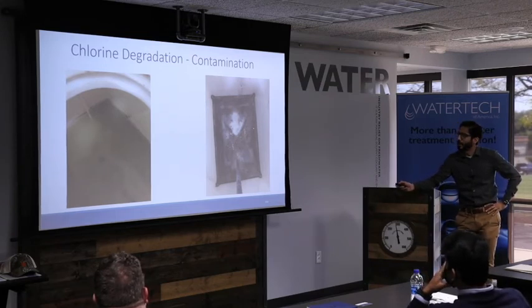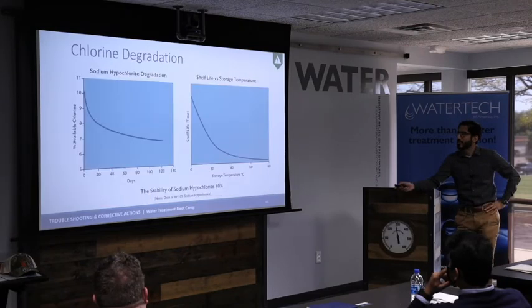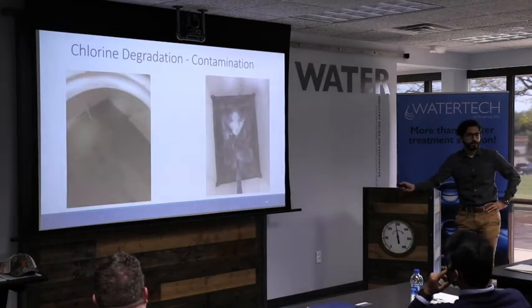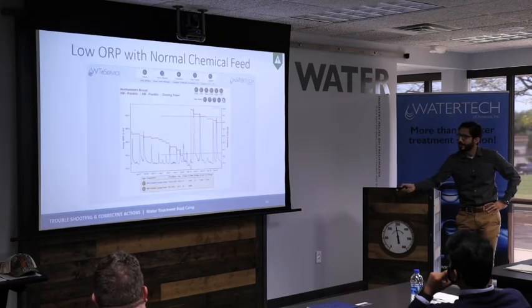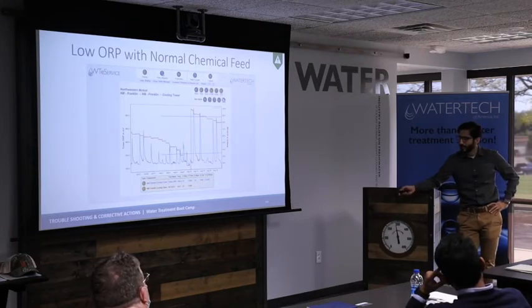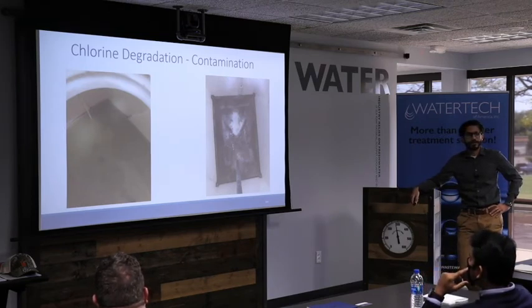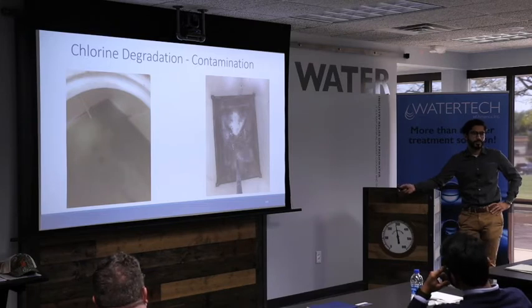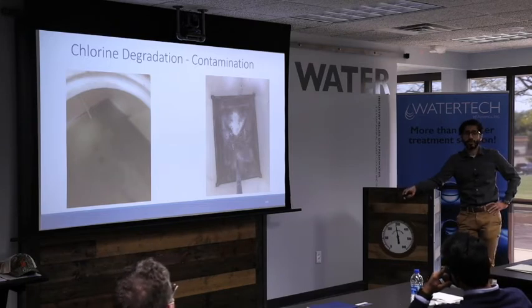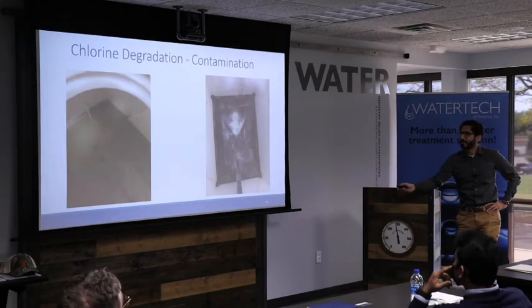The gentleman or whoever it was just left the chlorine and the screw in there, and what happens is it starts oxidizing. It starts reacting with the chlorine. So we actually went through three drums of chlorine because every time it would lose strength, and lose strength very quickly, because of the little screw. So we emptied out the tank, we rinsed it out, and still we had the same problem. The problem only went away once we replaced the tank altogether. So just that little piece of screw.